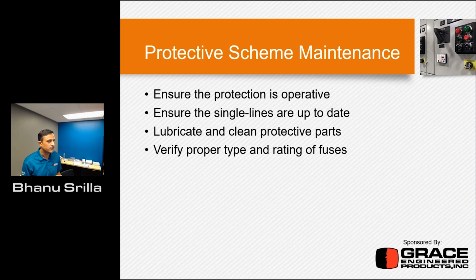Protective scheme maintenance: ensure the protection is operative, ensure the single lines are up to date, lubricate and clean the protective parts, and verify proper type and rating of the fuses. Whenever you replace the fuses, you have to replace them with the proper type and rating, so the functionality is not compromised, okay?